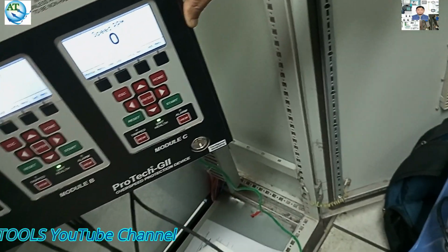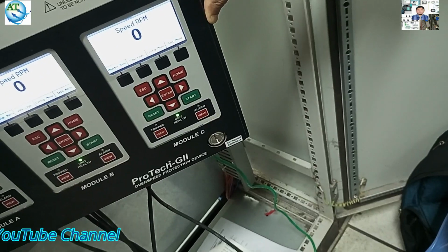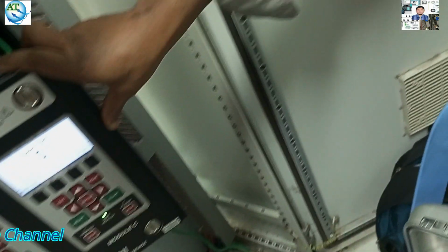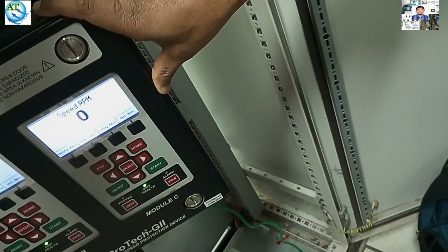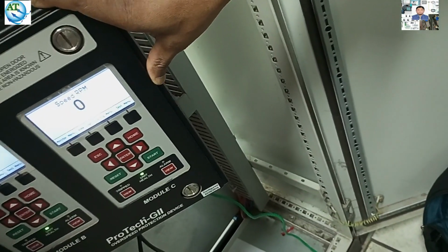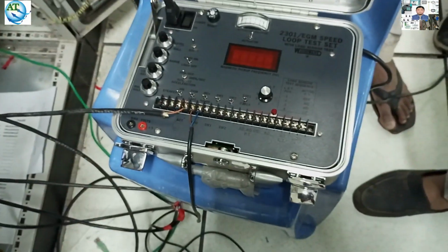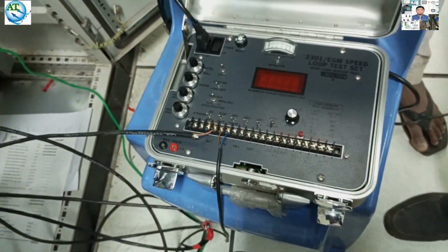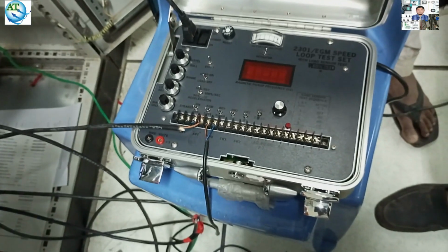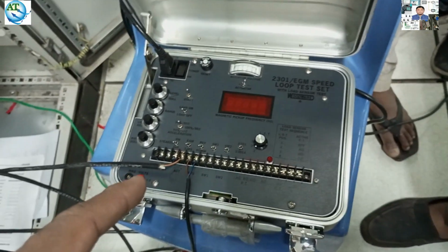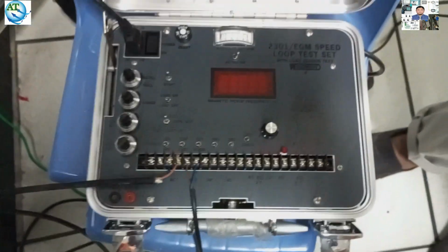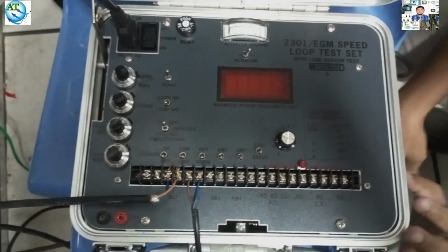We can also notice whether the supplied RPM and the displayed RPM in the Overspeed protection device and the Peak 200 terminal are the same. If the same supplied value is shown in the Overspeed protection device and the controller, then we can understand that our Overspeed protection device and the controller are working properly.